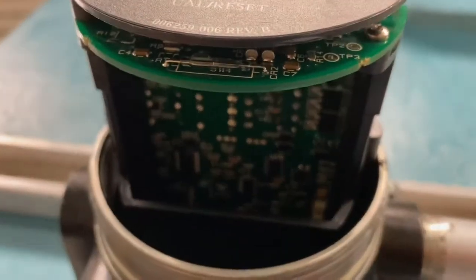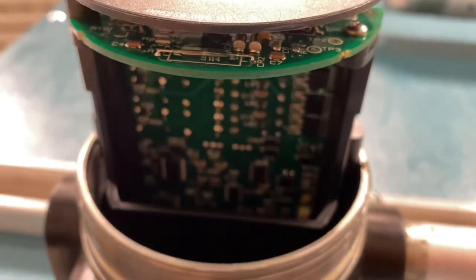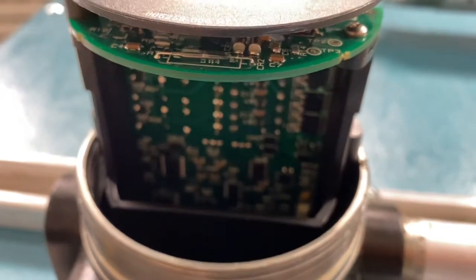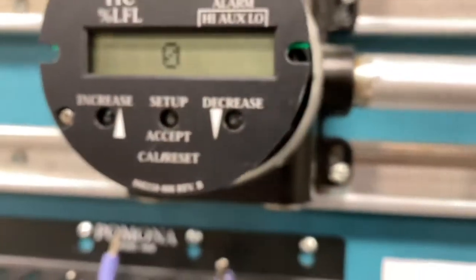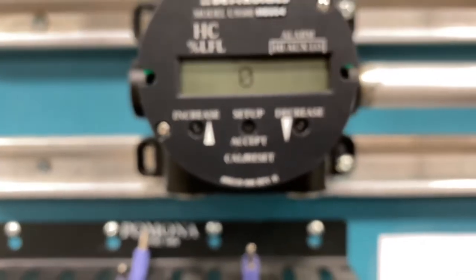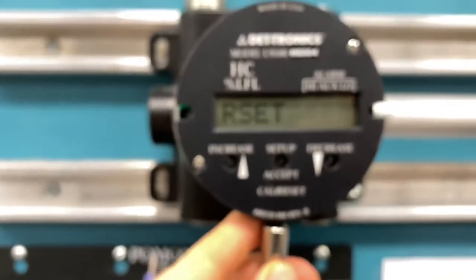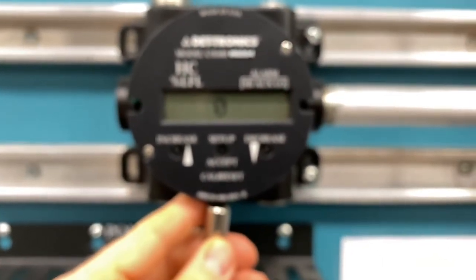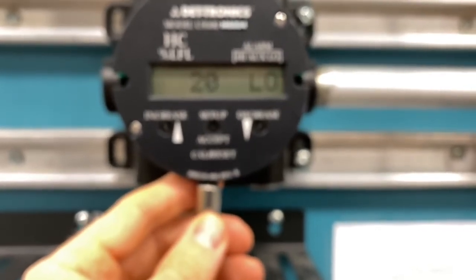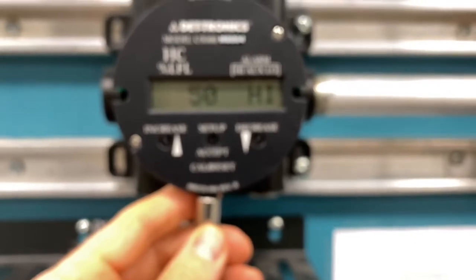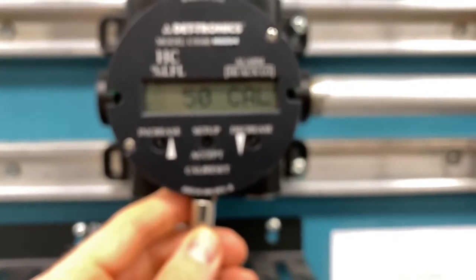When you wave a magnet over it, see if I can get this to focus a little better, it closes two pieces. There's a set of contacts in there that close when you wave a magnet over it. So that's how we get it into calibration mode. I've got a magnet here, and if I wave this magnet under the bottom, you can see the screen changes. I think we need to hold it for 9 seconds, and it should cycle into a...